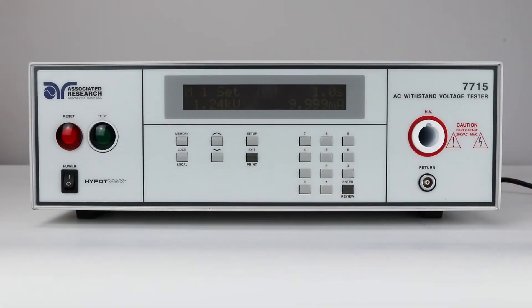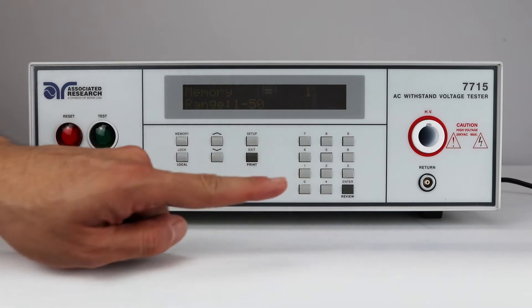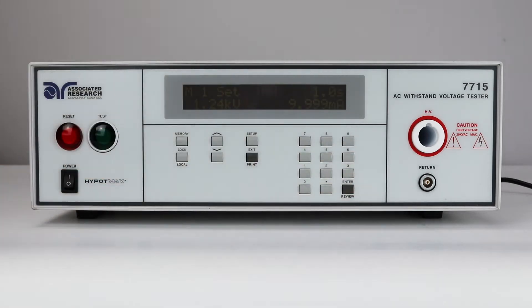First, we're going to set up an AC HiPot test in memory 1. Press the memory key, use the numeric keys to enter the memory location number, and then press the enter key. For this video, we will use memory location 1. The program will recall the test parameters stored in this location and return to the operation mode automatically. The HiPot Max series instruments have a total of 50 memories.